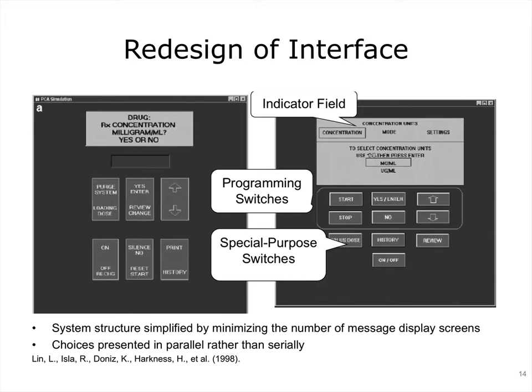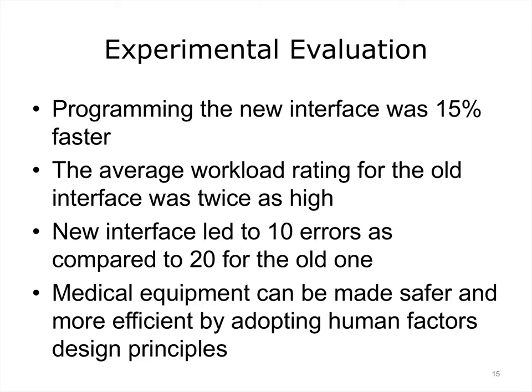The old and new interfaces are illustrated on the slide. The new system was designed to simplify the entire process and provide more consistent feedback. For example, the system structure was simplified by minimizing the number of message display screens, and choices were presented in parallel rather than serially. It's important to note that the revised screen was a computer simulation and was not actually implemented in the physical device. They conducted a cognitive study with 12 nurses comparing simulations of the old and new interface. They found that programming the new interface was 15% faster, the average workload rating for the old interface was twice as high, and the new interface led to 10 errors compared to 20 for the old one.